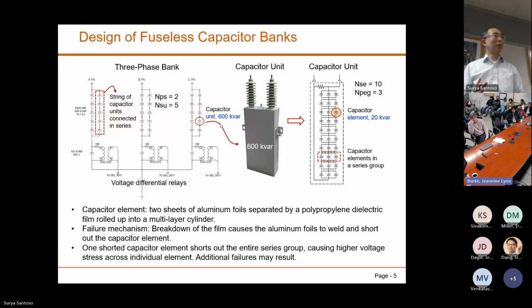The second possibility is that if some elements already fail, and then additional elements continue to fail, such that the differential voltage is now above the threshold, one of the relays is going to send a trip signal to the circuit switcher, and the circuit switcher will open. That will create what we call nuisance tripping, or involuntary de-energizing.